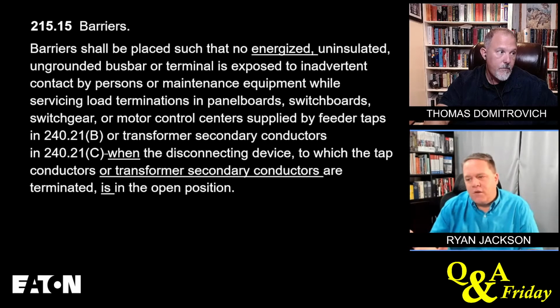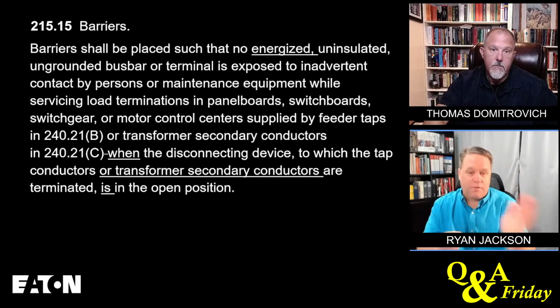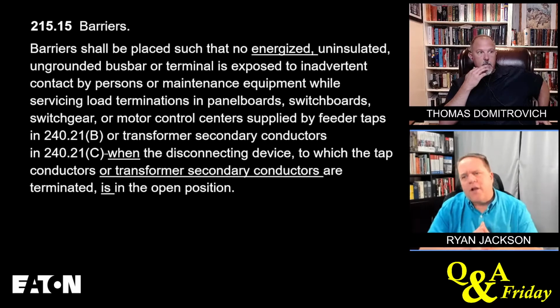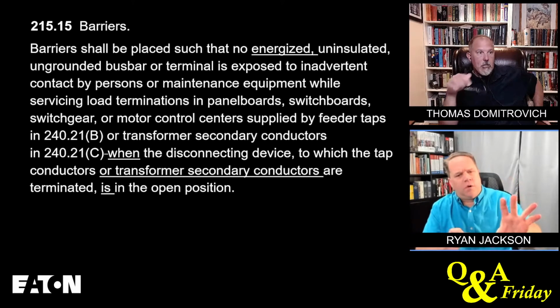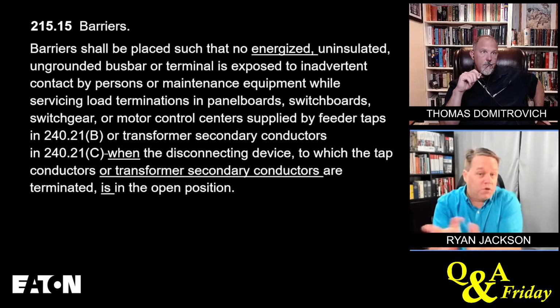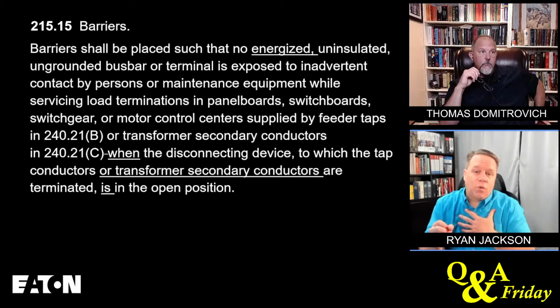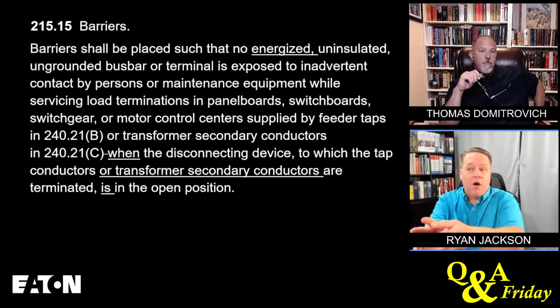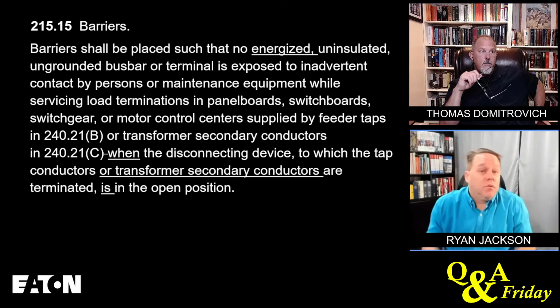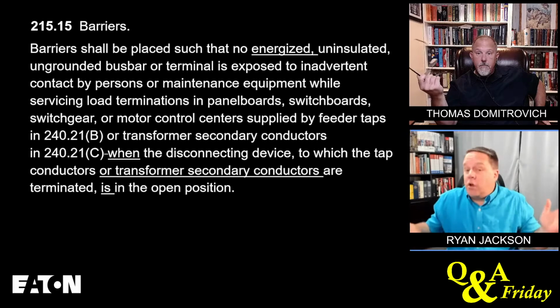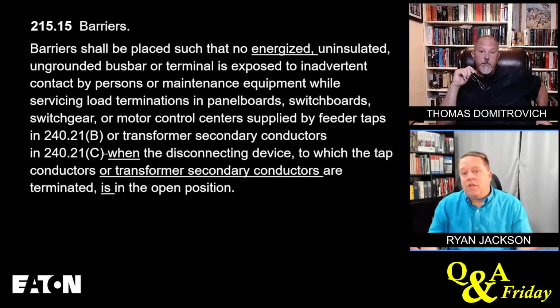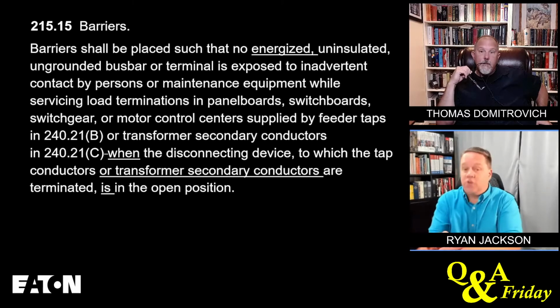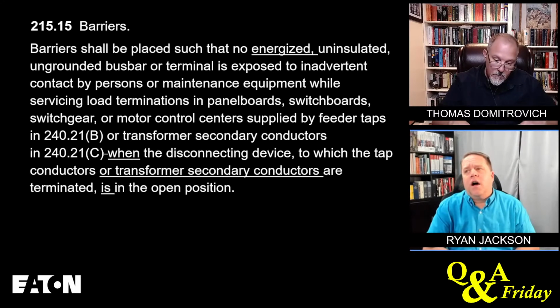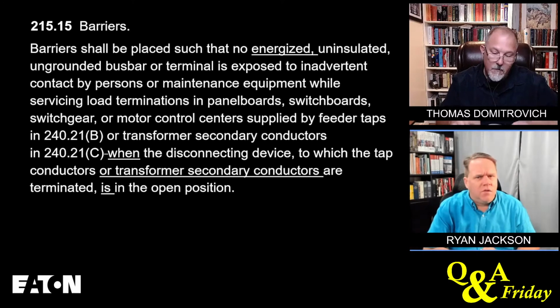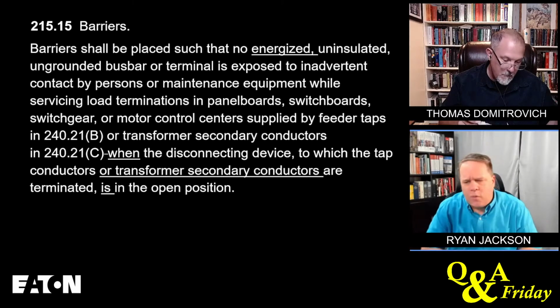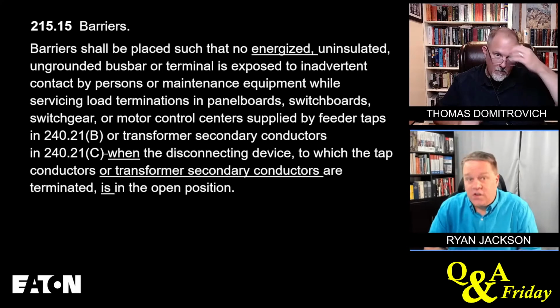On the other 1%, when we have a delta or single phase, 480 to 120 or something, on those other applications, usually the transformer is only going to be supplying one piece of equipment. And me as an electrician, if I have to work in that one piece of equipment, that downstream device, I could just open up the primary overcurrent device and remove the hazard, if it's close by. If it's close by. And remember, 450.14 says that the transformer has to be marked to indicate the location of the primary disconnect if it's not within sight. Correct. And 312, I think maybe it's 312.8 or so, we have to label the panelboard to tell us where the source was. So we're making it easier for electricians to shut things off. Right.